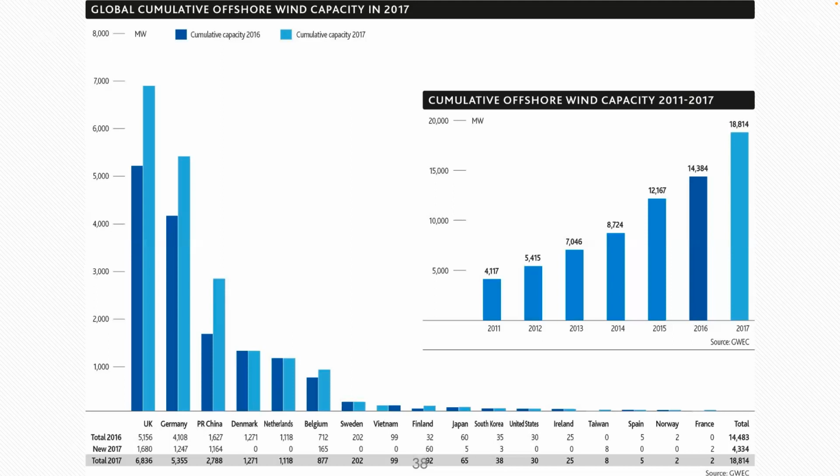Yeah, so capacity factor is about the maximum theoretical power generation, and it should include fundamental efficiency things within the turbine itself. It's not talking about the percent of energy captured out of the wind. It's talking about what percentage of the maximum power generation of the turbine itself is being produced over an average time period. So it should be inclusive of those things. Yeah. Okay.